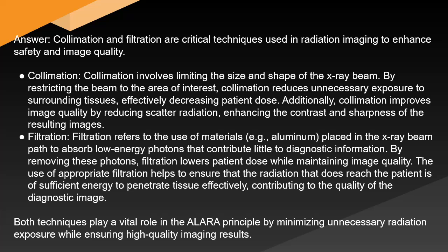Filtration. Filtration refers to the use of materials, e.g., aluminum, placed in the X-ray beam path to absorb low-energy photons that contribute little to diagnostic information. By removing these photons, filtration lowers patient dose while maintaining image quality. The use of appropriate filtration helps to ensure that the radiation that does reach the patient is of sufficient energy to penetrate tissue, effectively contributing to the quality of the diagnostic image. Both techniques play a vital role in the ALARA principle by minimizing unnecessary radiation exposure while ensuring high-quality imaging results.